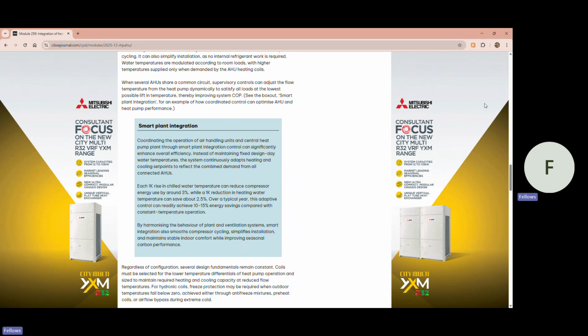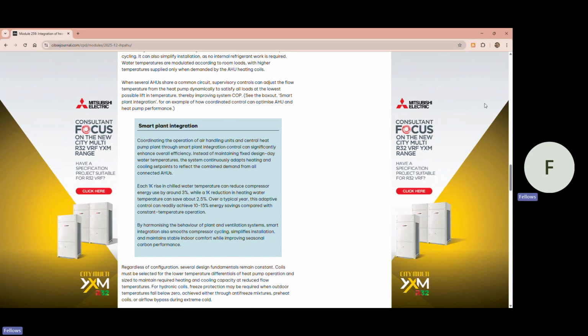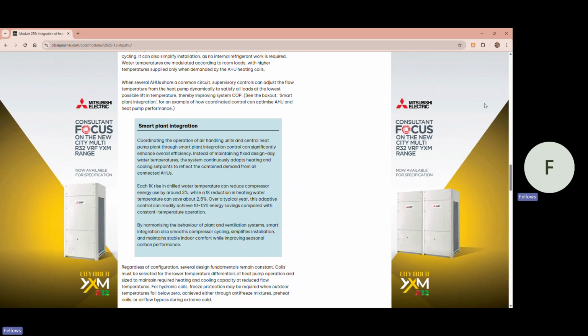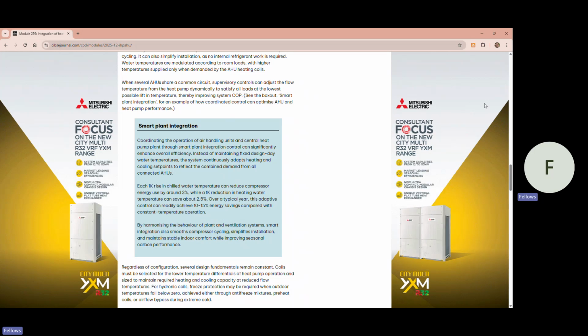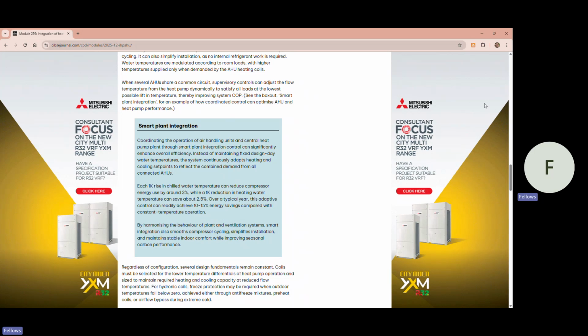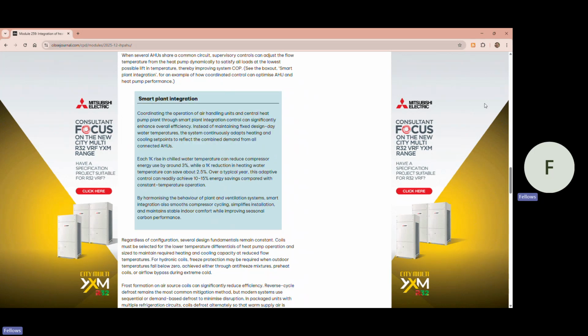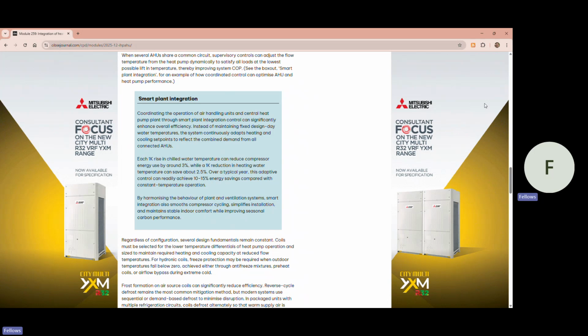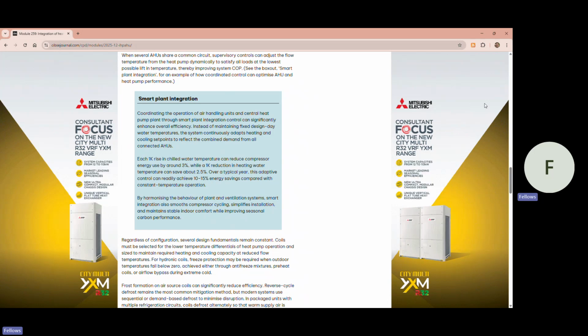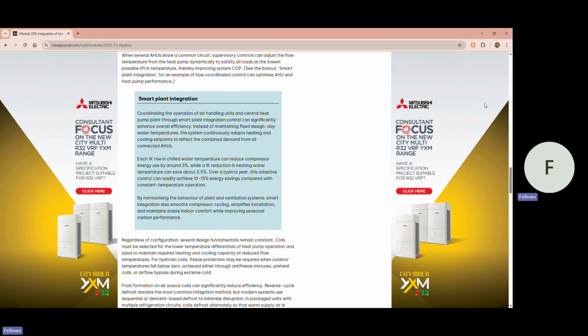Each 1K rise in chilled water temperature can reduce compressor energy use by around 3%, while a 1K reduction in heating water temperature can save about 2.5%. Over a typical year, this adaptive control can readily achieve 10 to 15% energy savings compared with constant temperature operation. By harmonizing the behavior of plant and ventilation systems, smart integration also smooths compressor cycling, simplifies installation, and maintains stable indoor comfort while improving seasonal carbon performance.